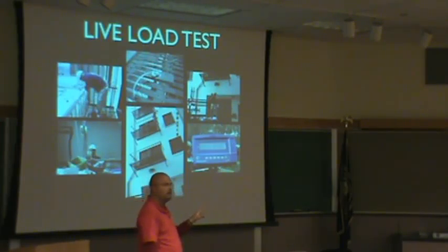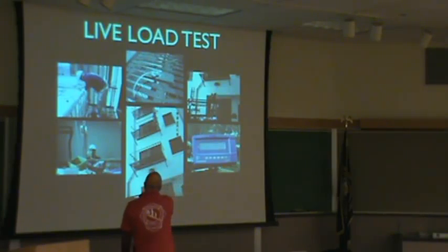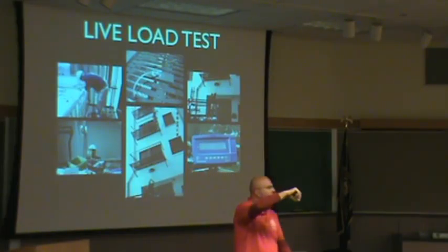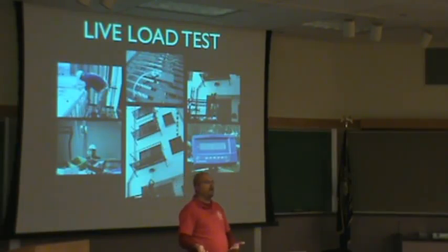This is a bit of a load test. I needed almost 3,000 pounds. I used the back of a truck which weighed 7,000 pounds. I had a cable that went through the building, through every one of these, plated and strategically angled so I was able to pull on this cable 3,000 pounds — using a chain fall, 10 stories. Everyone had to be measured, taped, photographed, and videotaped. How much of that buys bolts or pays for the client? None of it. That's why load tests are not the most economical way of taking care of your fire escapes.